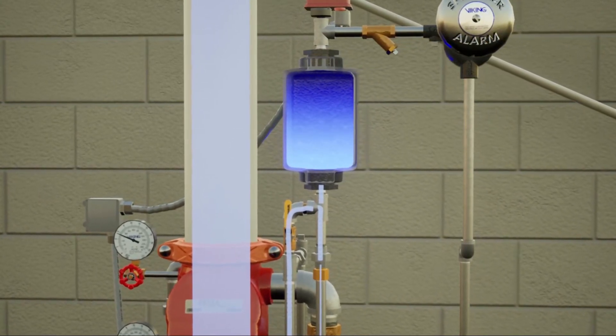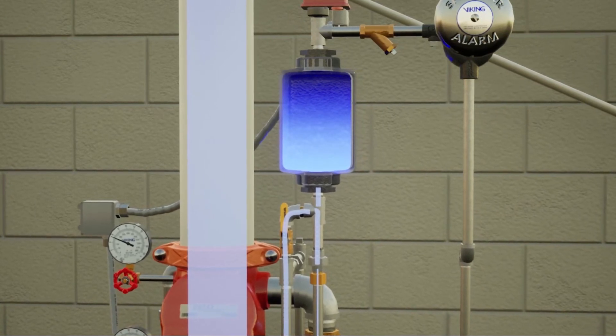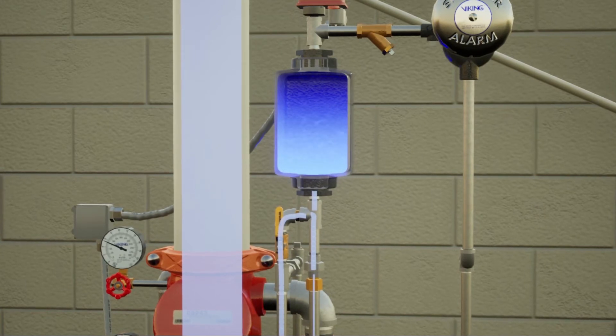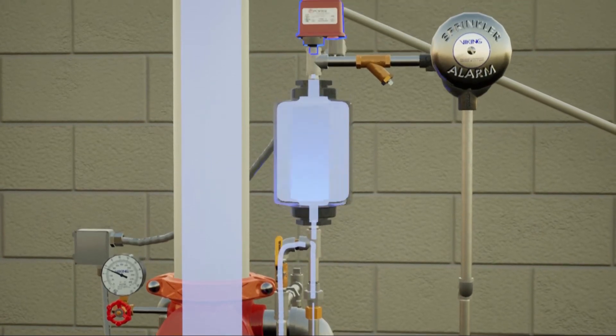During a fire, a consistent flow of water enters the alarm trim and fills the retard chamber faster than the restriction can drain, and the water flow continues through to the alarm devices.